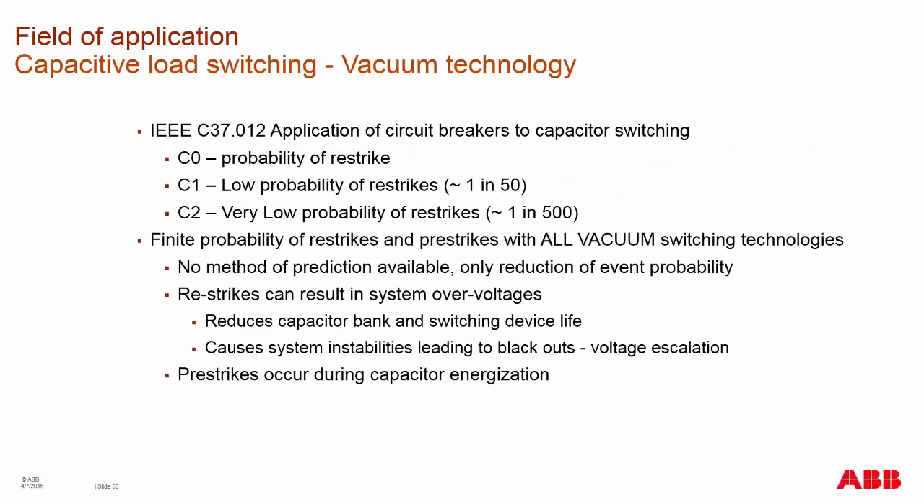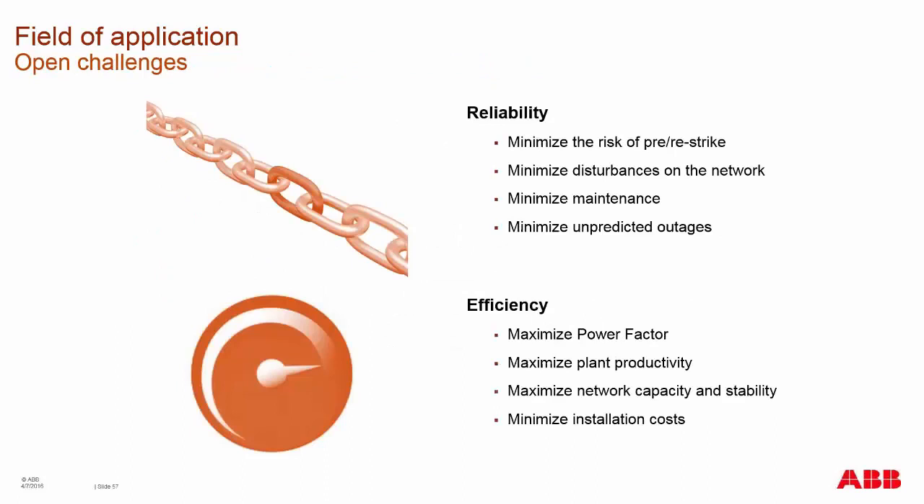With the capacitive load switching standards we saw previously on a circuit breaker — probabilities of re-strikes — you have no method of really predicting when you will have a re-strike or pre-strike. This causes system instabilities which can lead to voltage escalation and potentially a blackout due to component failure. Pre-strikes happen during capacitor switching in, and re-strikes happen when switching the capacitors out.